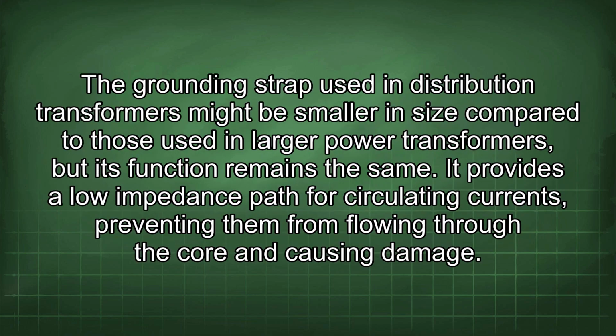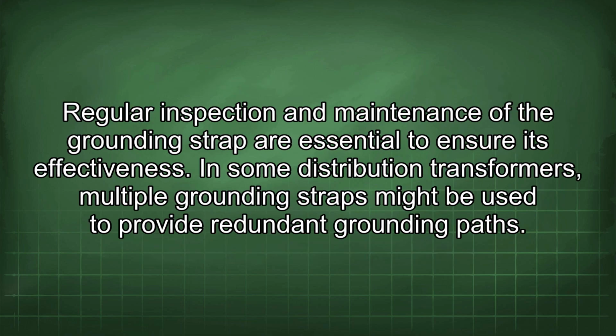The grounding strap used in distribution transformers might be smaller in size compared to those used in larger power transformers, but its function remains the same. It provides a low impedance path for circulating currents, preventing them from flowing through the core and causing damage. Regular inspection and maintenance of the grounding strap are essential to ensure its effectiveness.